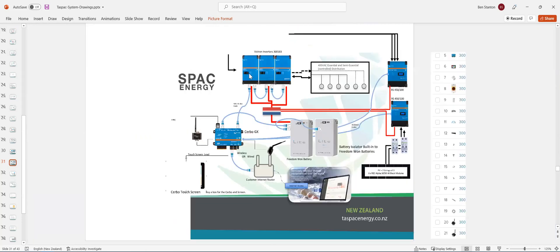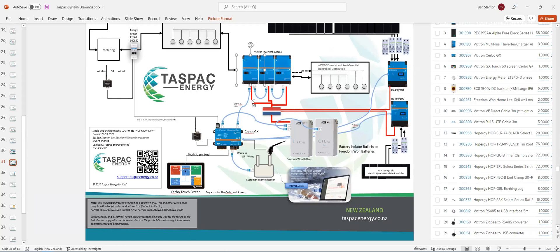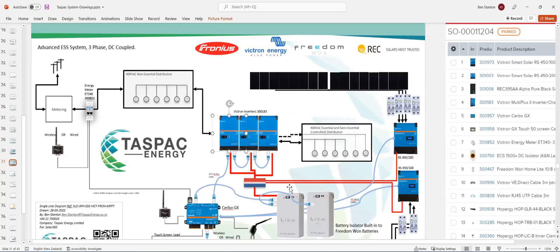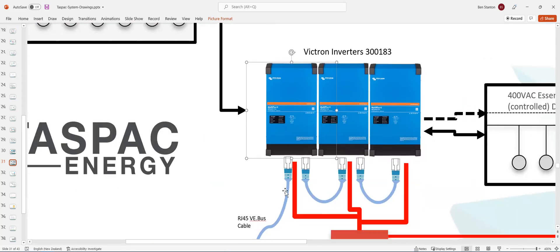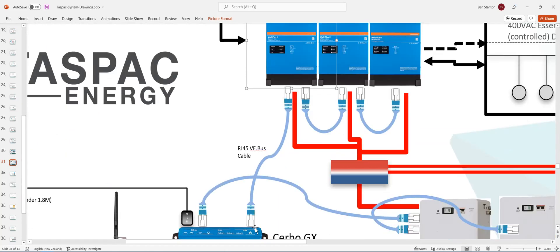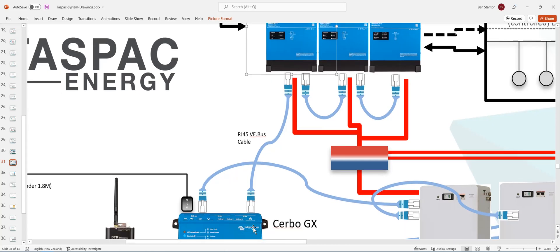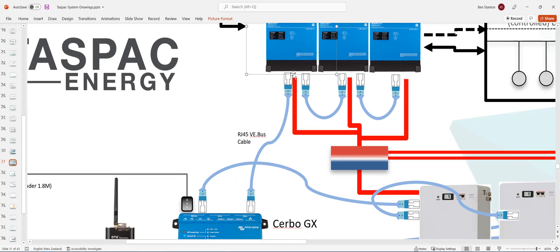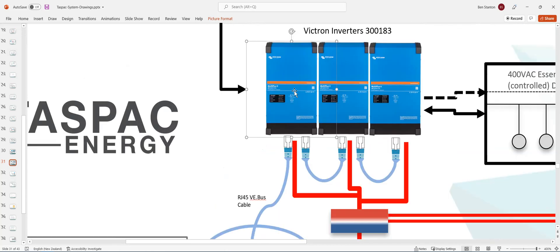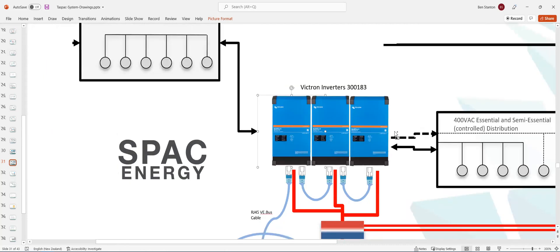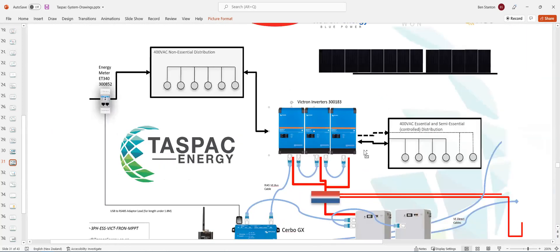Now, the inverters will connect using RJ45 cables. So they're going to still use an Ethernet cable, but it's the VE bus. It's actually plugged into the VE bus port. VE just stands for Victron Energy. VE bus port. And it goes from the Cerbo GX up to the inverter, first inverter. And then there's two VE bus ports on each inverter. Then click through to the other inverter, click through to the other inverter. And then an end-of-line resistor on that.